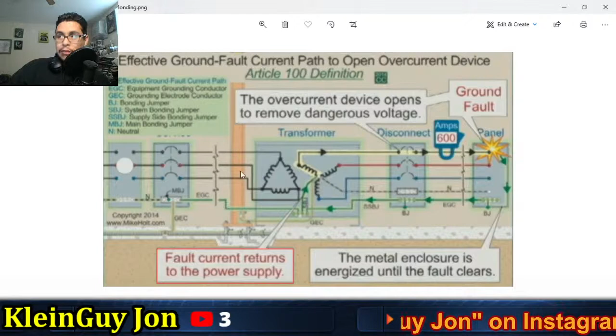So right here at the winding, you come out with your supply bonding jumper, or I'm sorry, the system bonding jumper. You bring it to the terminal, or if you're going to ground this, you need a grounding electrode conductor, you can also bond it and bring it to the structural steel. Okay. Now, here's the thing.